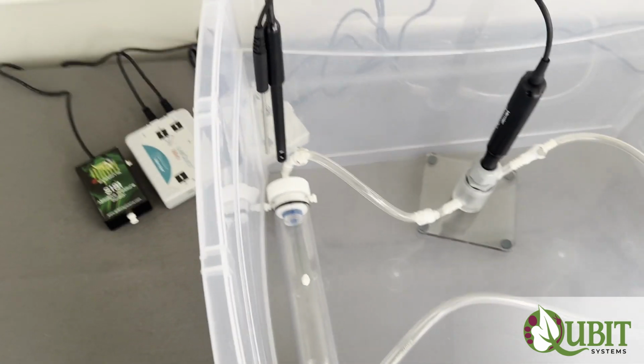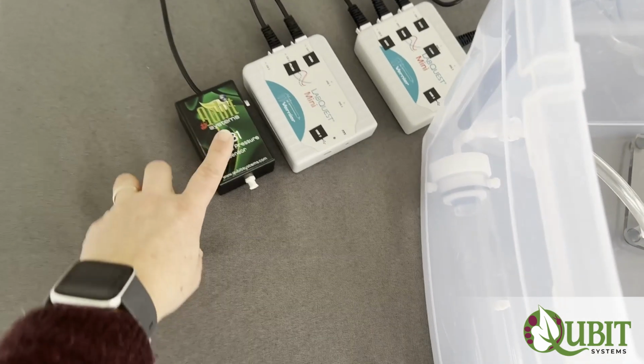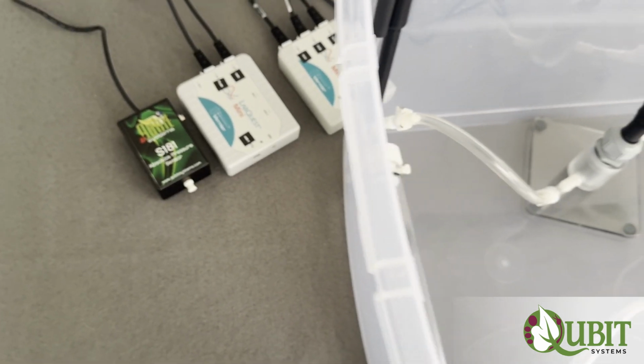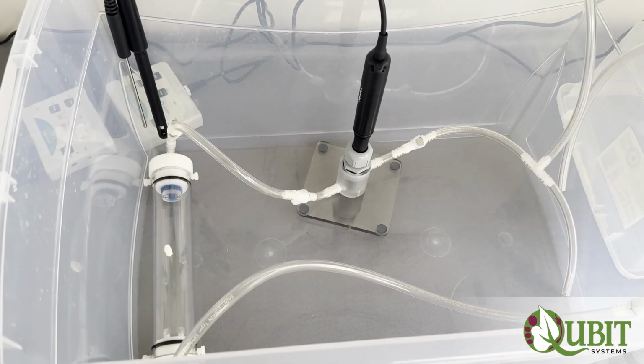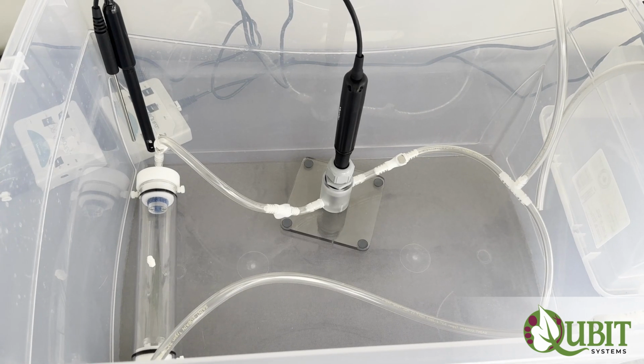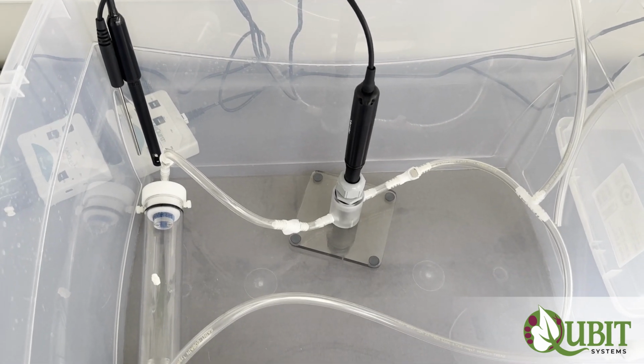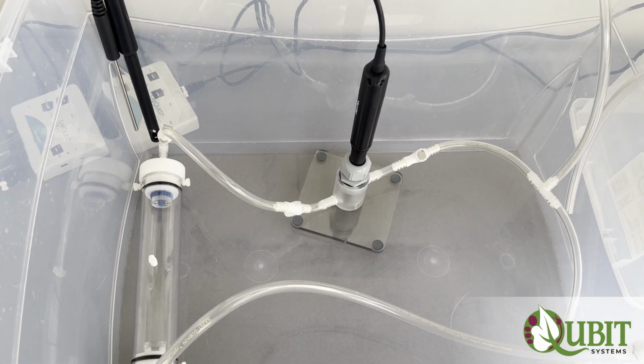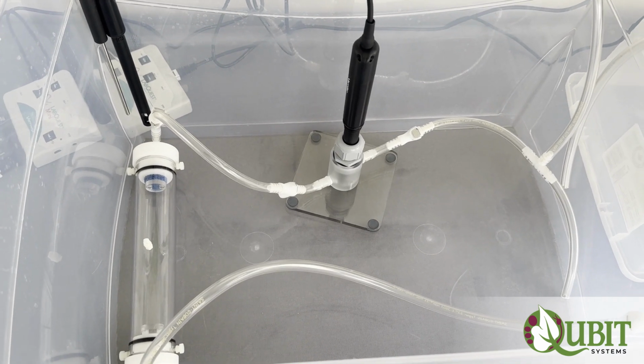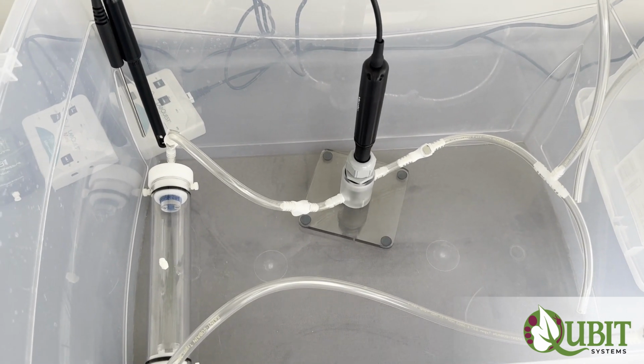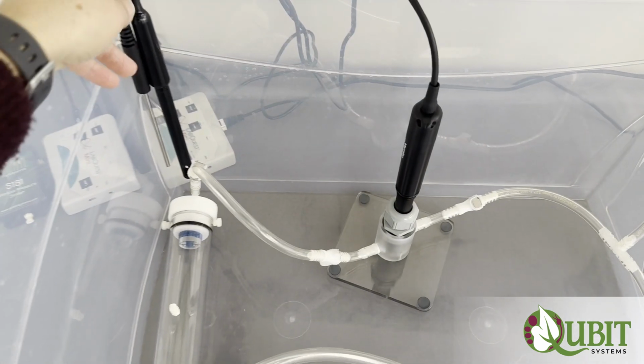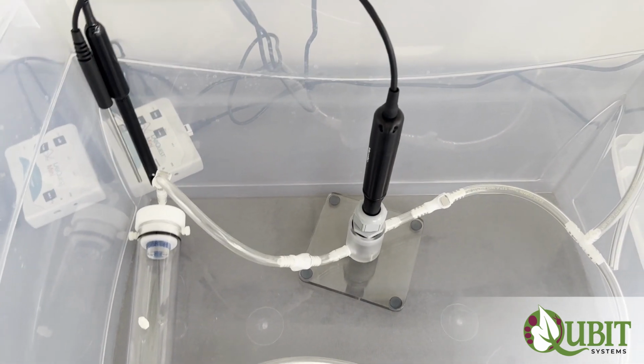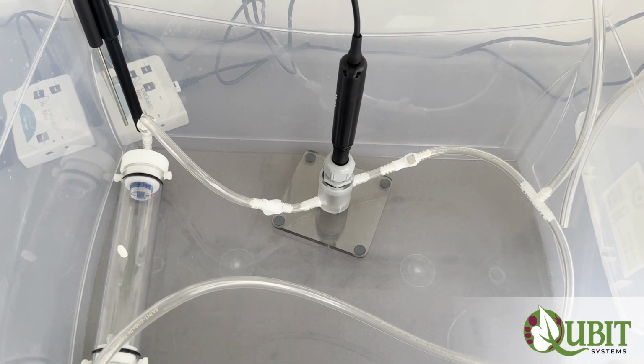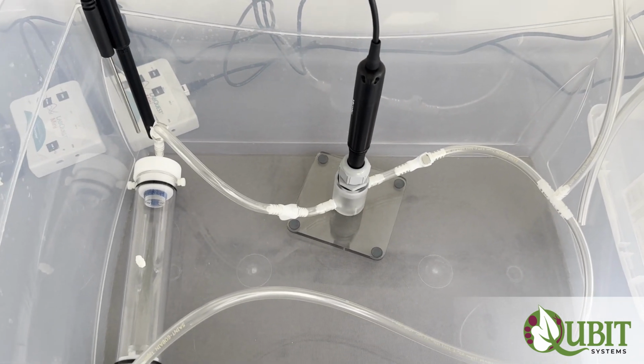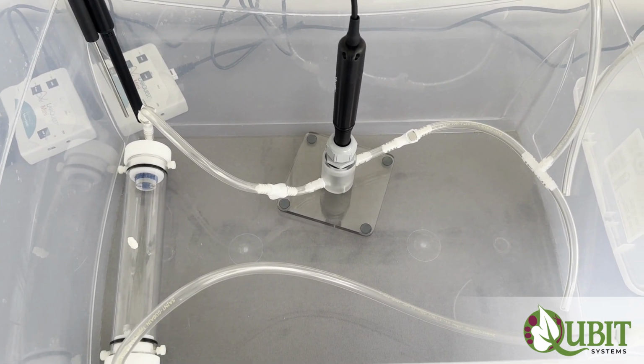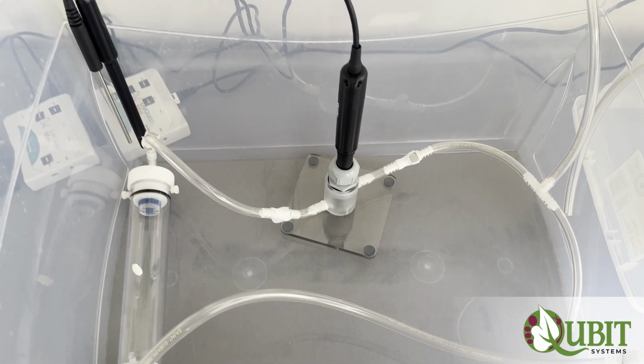In addition to DO, salinity, and temperature, the system also has an absolute pressure sensor, which is important because you need the measure of atmospheric pressure during calibration of the DO probe. The values that are used in this package are in milligrams per liter, and they change with atmospheric pressure and temperature. So during calibration, you need to know what that temperature and pressure are, and you can obtain the values of DO in those conditions directly from a table that we provide in the manual.